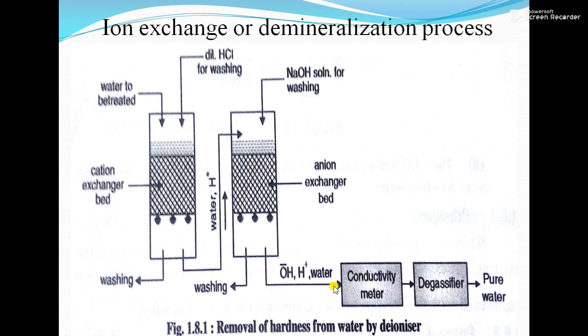Then the water will go to the conductivity meter and then to the degasifier. If any gases are present, those gases get removed. After a certain time, the cation exchanger bed as well as the anion exchanger bed get exhausted. That can be removed and regenerated by dilute HCl and dilute NaOH.